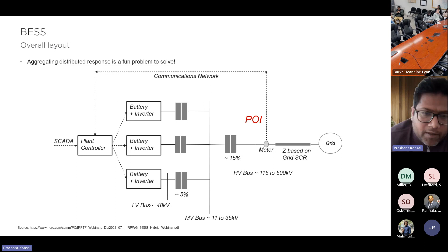So about battery storage specifically, there are really 2 things you want from the perspective of real-time control: reactive power and real power. So those are the 2 core controls. If somebody gives a real power command to the battery, you have to provide that real power at the POI, so there is some basic control around it. There is some reactive power control — if you need reactive power or want to maintain a site voltage or power factor, that control is part of the core control of any battery storage plant.